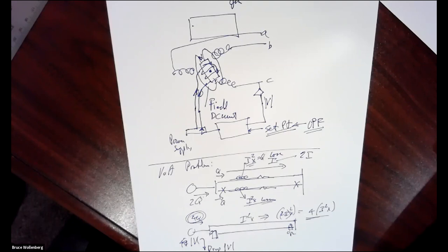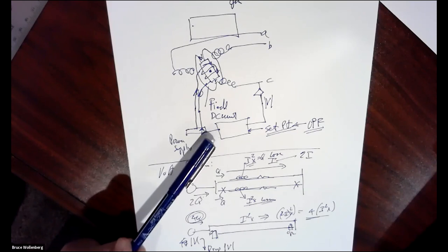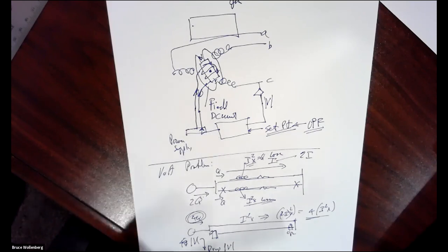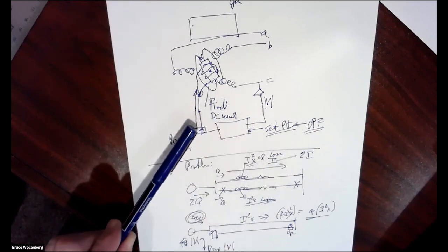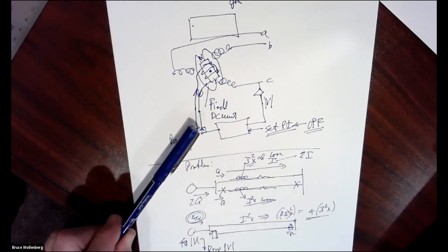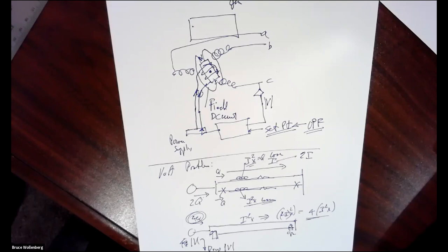And so reactive loading has become very, very important, and there have been various outages in the world. There was one in 1978 in France where they attributed the collapse itself to voltage collapse, the new terminology. And that spawned a lot of studies on voltage collapse phenomena. But again, I don't think operators get into the voltage too much. They may have optimal power flow trimming it up and down to try to minimize losses and things like that. The real worry is this situation where suddenly I need more reactive power and the voltage regulator hits its max and you can't put out any more Q.